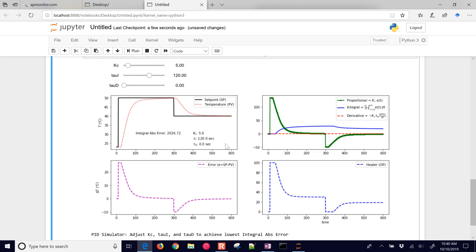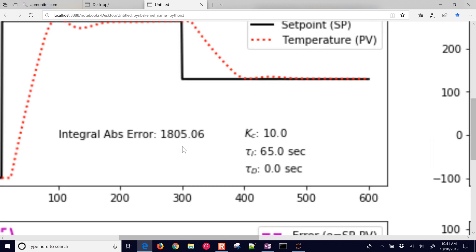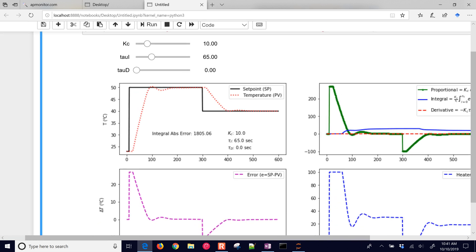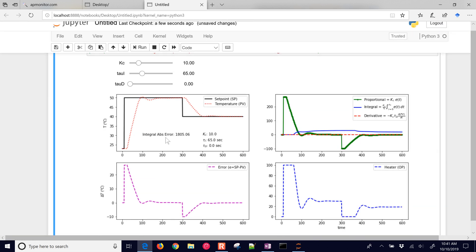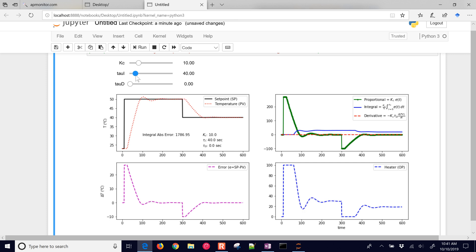This is going to bring up the PID tuning interface. We can adjust the KC value and the integral time constant — I'm going to lower it a little bit. Pay attention to the integral absolute error. It's 1805 right now. As I reduce it, it goes to 1785, then a little bit lower still. If I go too low, it's going to have more oscillation and get worse. The optimal integral time constant seems to be somewhere around 45 to 50.